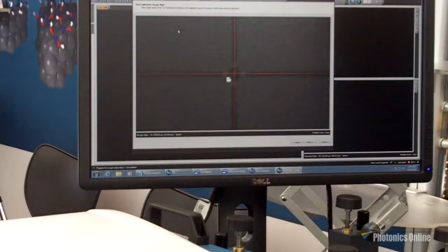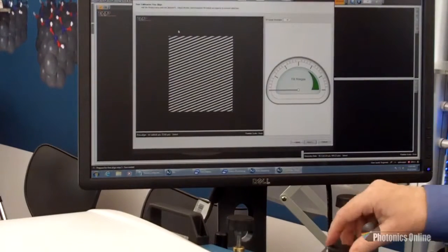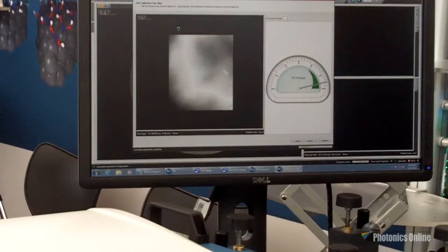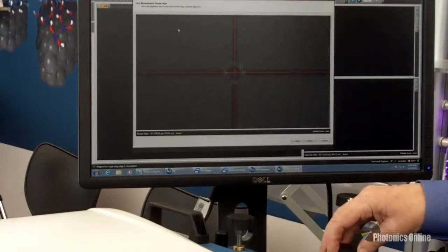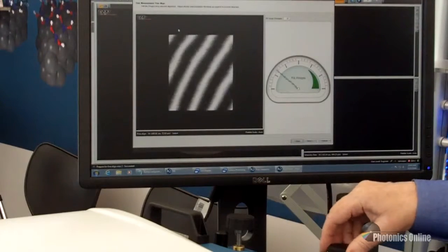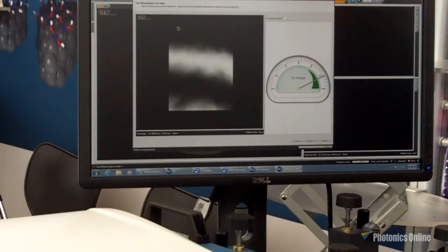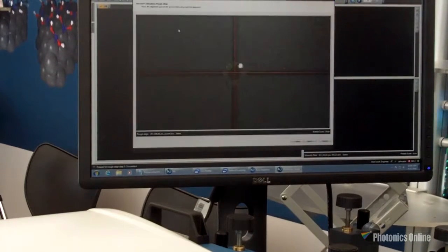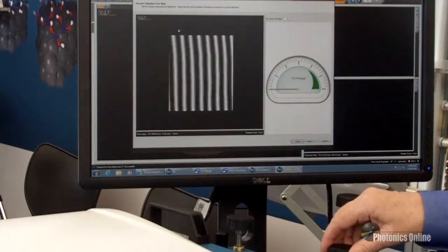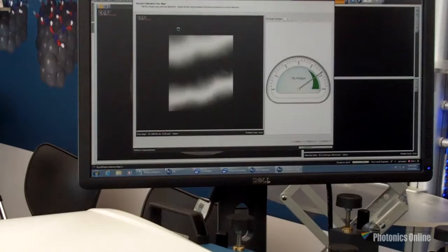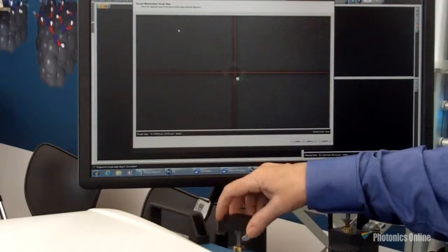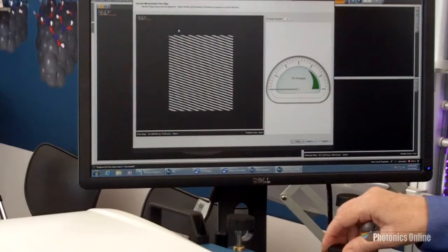Again, this is one step in a calibration mode, wizard-based, to allow me to optimize the ideal amount of tilt being introduced to register any system error that would normally be inherent, which will be calibrated out through this sequence. So I'm introducing tilt from four different directions and doing this one time through for a given measurement situation to effectively calibrate out the system error from my final measurement.